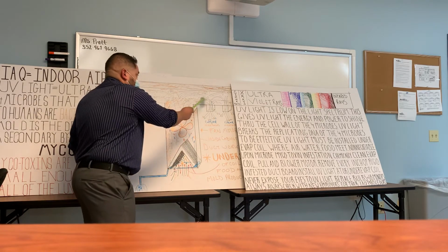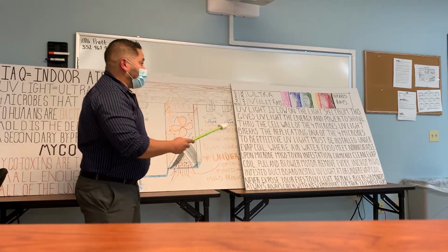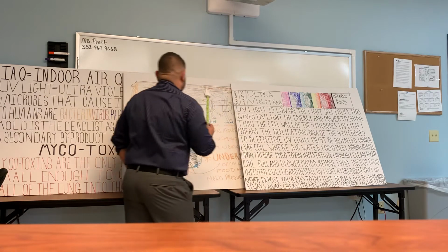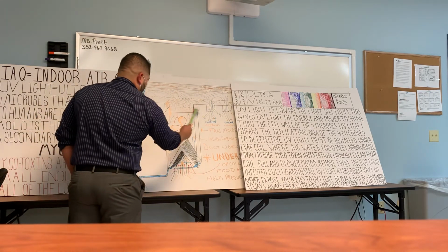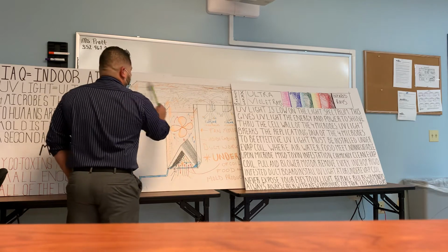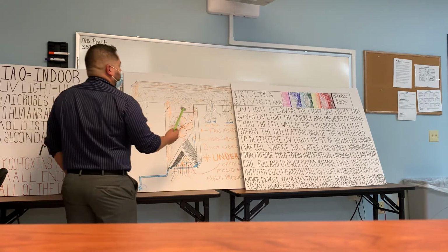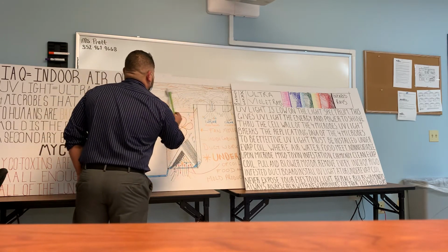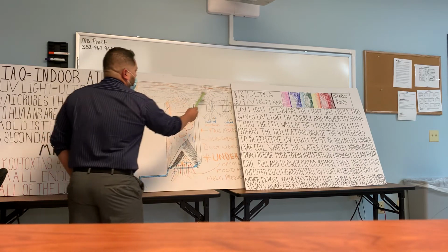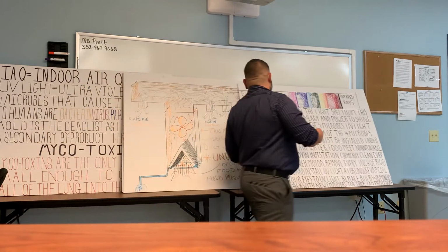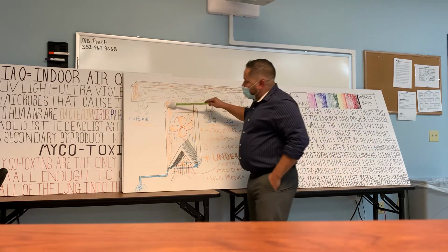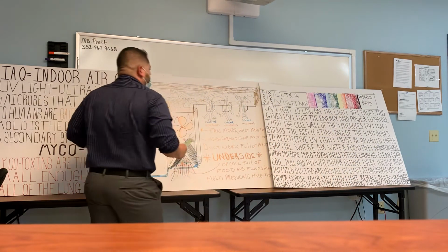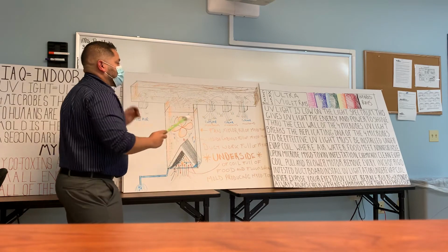This has mycotoxins in it. This isn't going anywhere. And when I say every inch of it, we mean sometimes you'll come up on a job and say, this is in the closet, this is in the attic. And somebody replaced the ductwork, but they left this riser original. Yeah, they cut all this off, they cut this off, and they added ducts, but they still left a piece of fiberboard here, full of mycotoxins. That's going to reinfest the rest of the system.